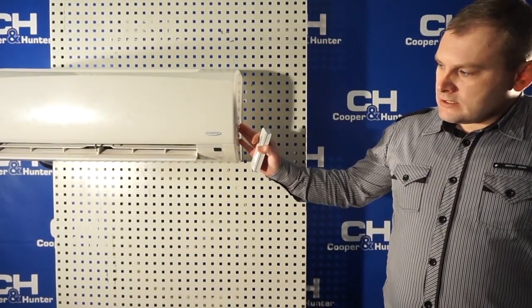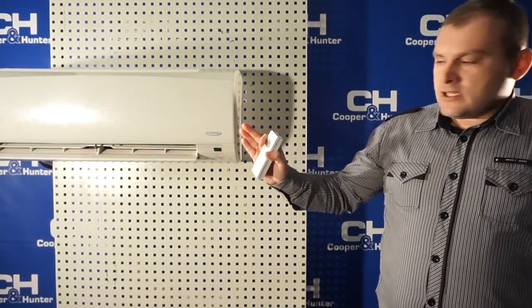It is the error of the fan motor of the indoor unit. It means the main board of the indoor unit does not receive information about the rotation speed of the fan motor of the indoor unit.